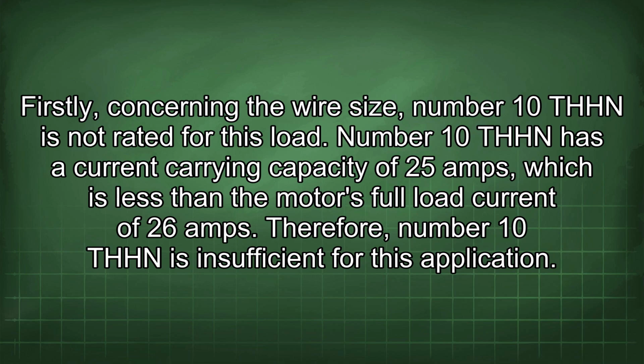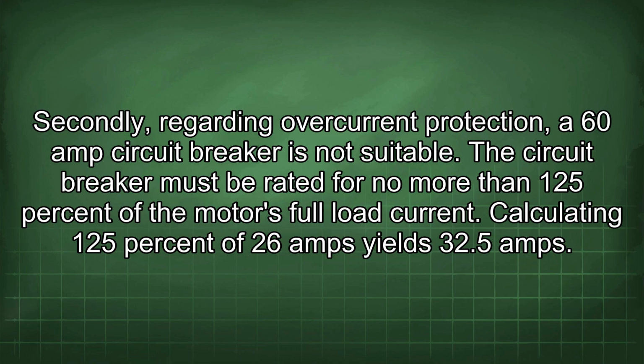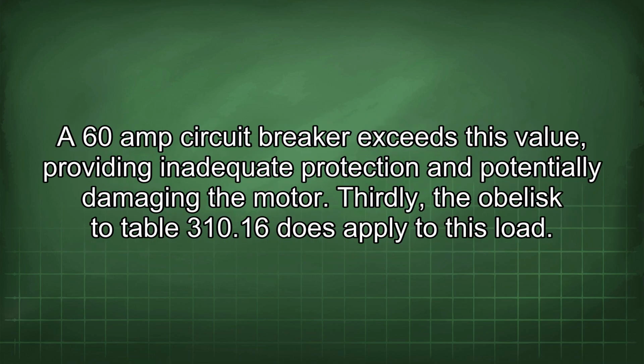Number 10 THHN has a current carrying capacity of 25 amps, which is less than the motor's full load current of 26 amps. Therefore, number 10 THHN is insufficient for this application. Secondly, regarding overcurrent protection, a 60 amp circuit breaker is not suitable. The circuit breaker must be rated for no more than 125% of the motor's full load current. Calculating 125% of 26 amps yields 32.5 amps. A 60 amp circuit breaker exceeds this value, providing inadequate protection and potentially damaging the motor.